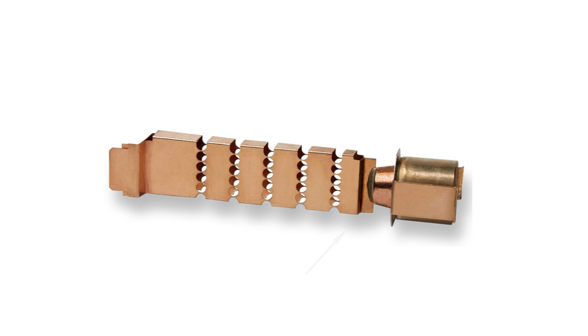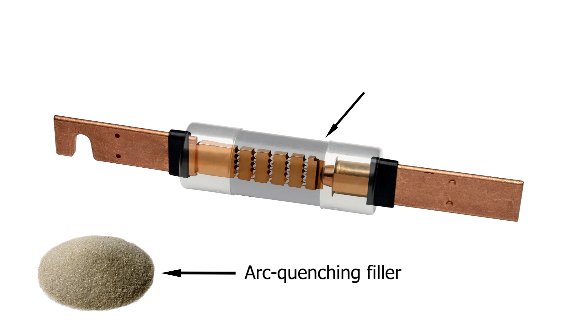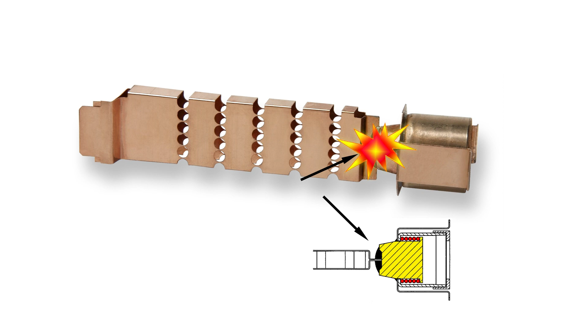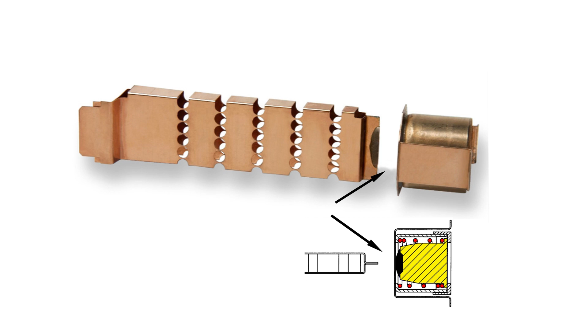Upon closer examination of the dual-element fuse link, we can see the two separate elements for overloads and short circuits connected in series. The filler material fills a tube surrounding the short-circuit element for superior arc quenching. Operation under persistent overload conditions causes the trigger spring to fracture the calibrated fusing alloy and releases the connector. The coiled spring pushes the connector from the short-circuit element and the circuit is interrupted.